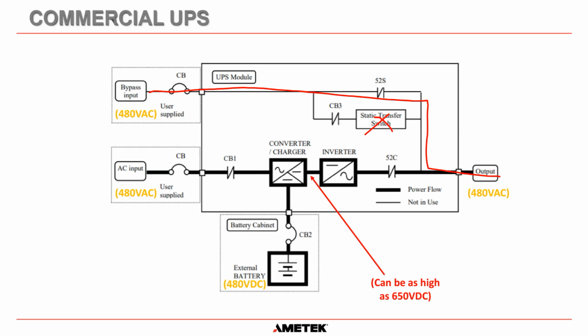Okay, so the contactor is designed to have a 100% rating of the power going to the load circuits. The static transfer switch in commercial UPS does not. Okay.